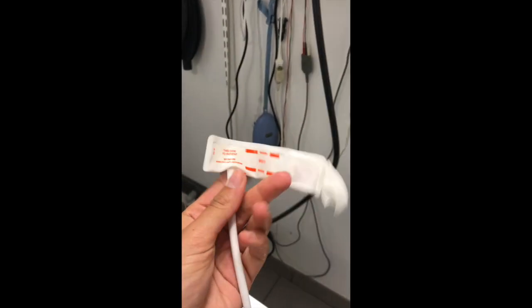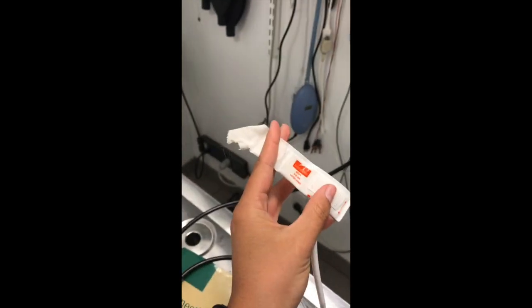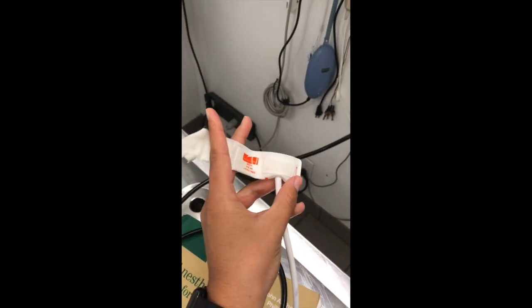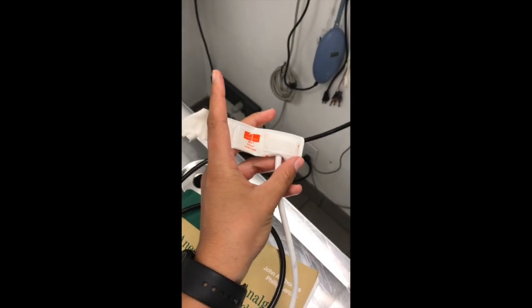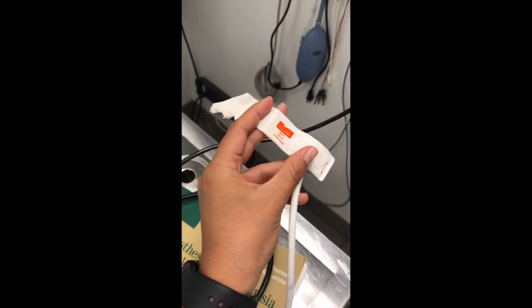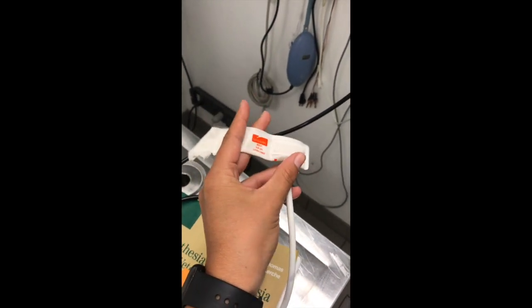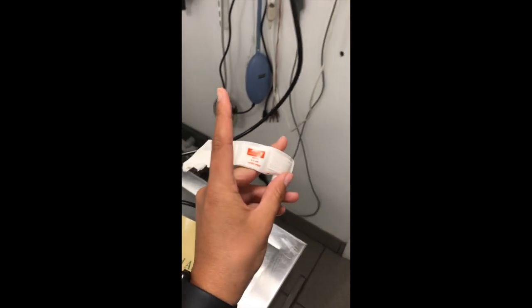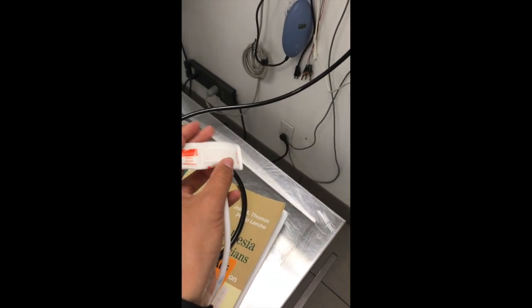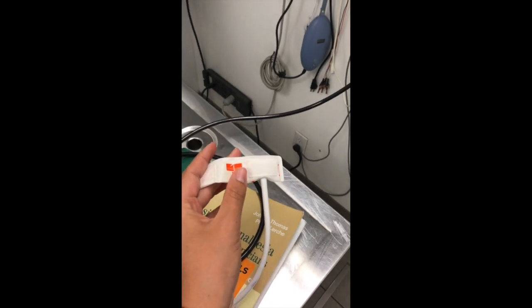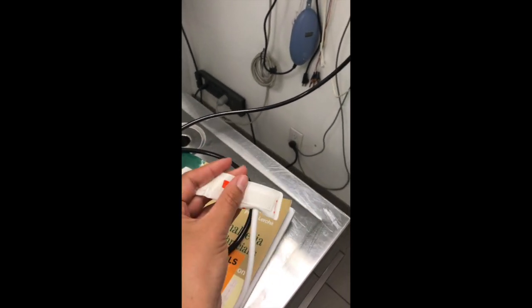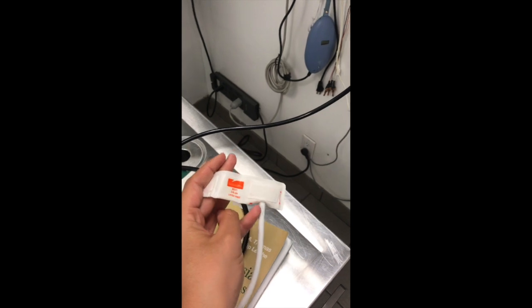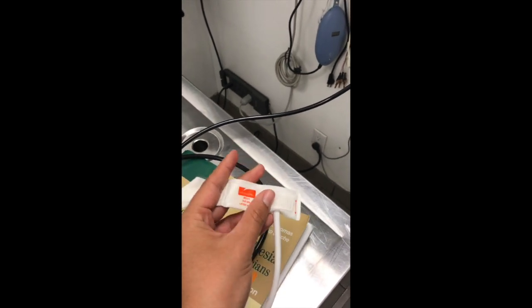Here is our cuff. Every size ranges depending on the animal. But specifically the width of the cuff should be about 30 to 50% of the circumference of the paw, of the leg. The cuff definitely should not be too firm or too tight. So how blood pressure specifically works, the cuff measures the oscillation in the cuff pressure, which is caused by the pulsations of the artery beneath the cuff.